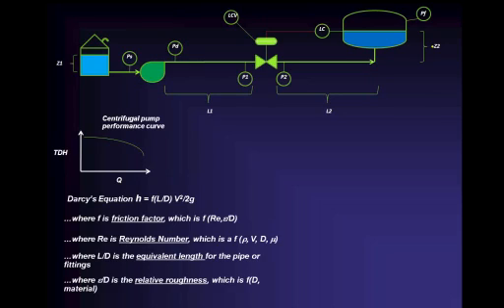The relative roughness ratio is a function of the diameter, the internal diameter of the pipe, and the material the pipe is made of. So we've got a different relative roughness number depending on whether the pipe is concrete or plain carbon steel. So, man, is there or is there not a whole bunch to think about when it's time to size a control valve and determine what the inlet pressure and the outlet pressure is? And I must say that all this stuff is your responsibility.